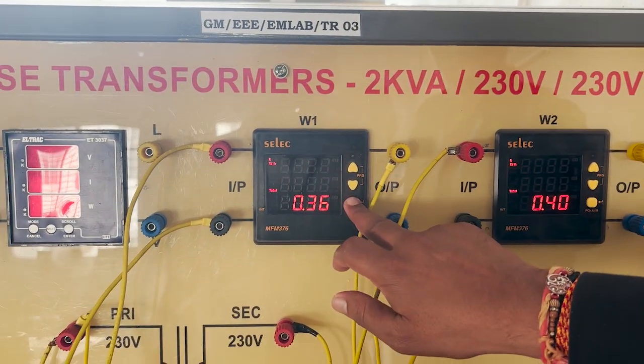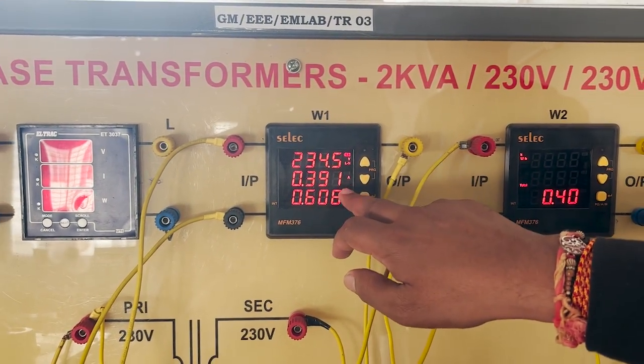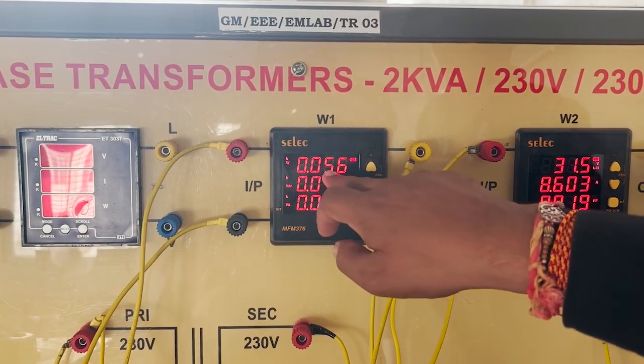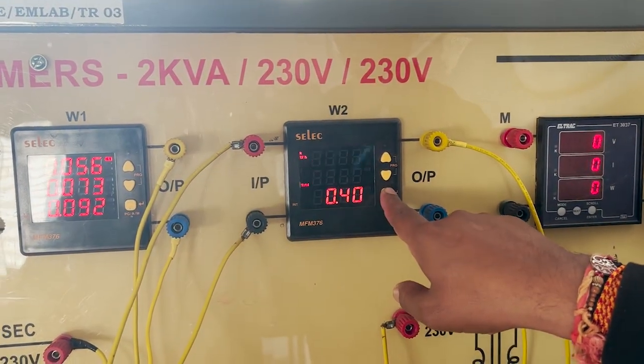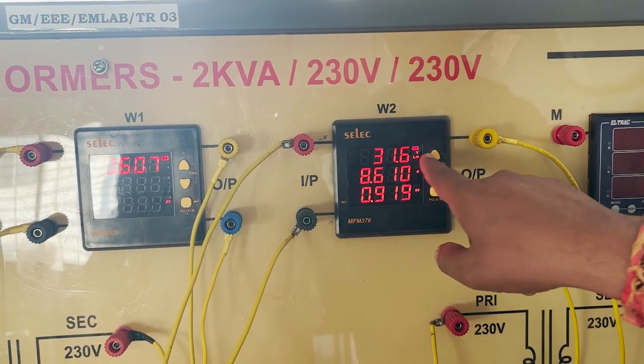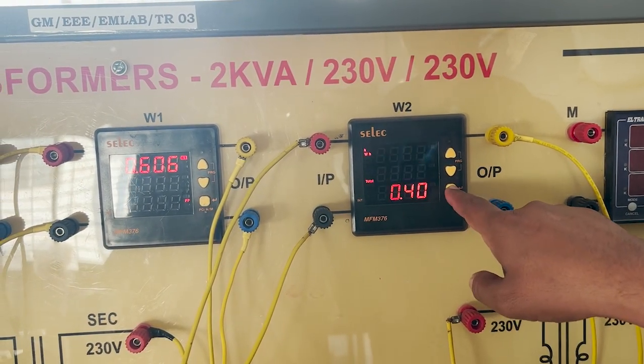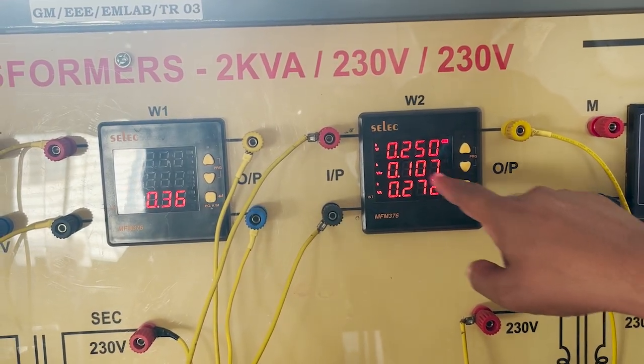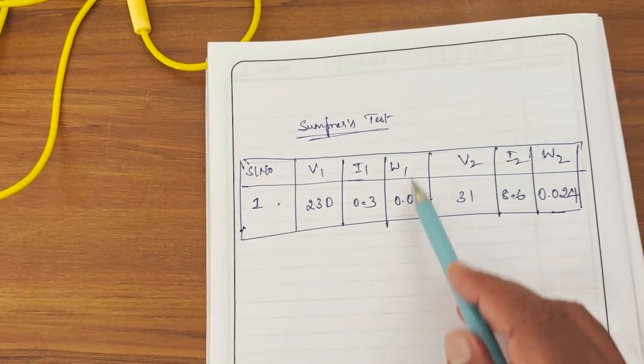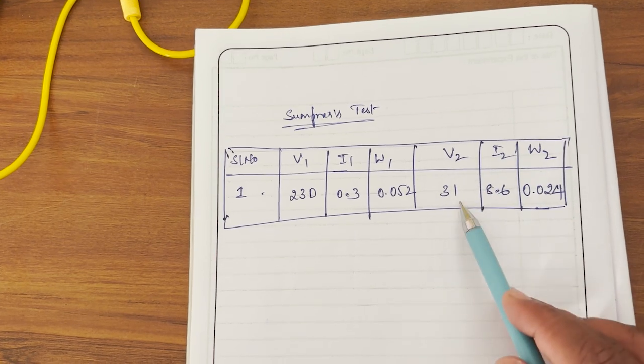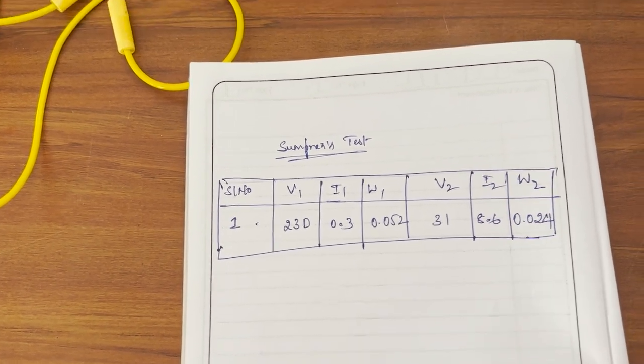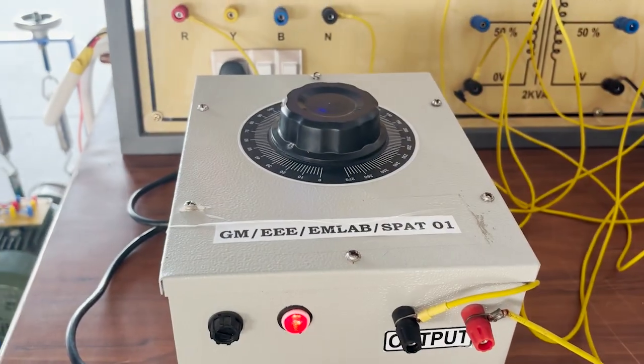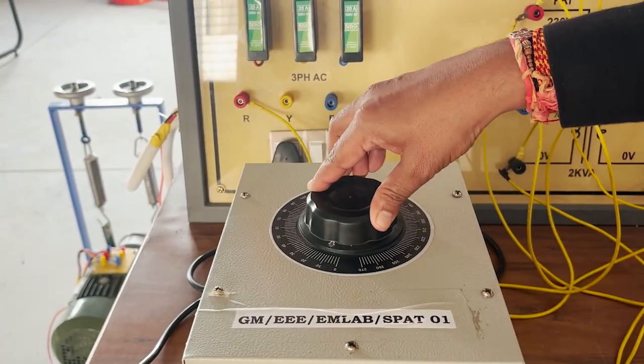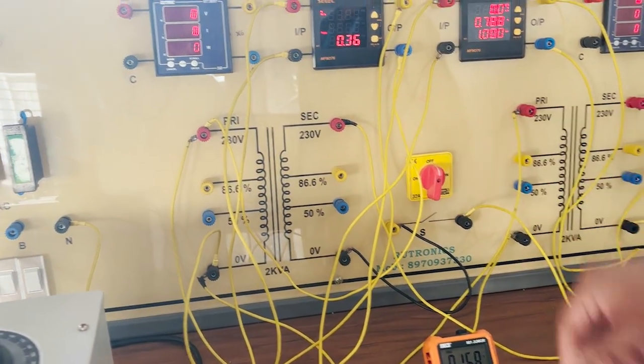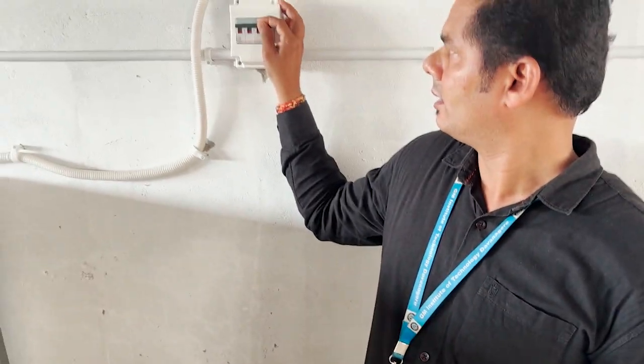Now we will take the readings, that is V1 is 234, I1 is 0.39, W1 is 0.056. Now W2, that is V is 31.6, 8.6 is the current and W is 0.250. Now you can see the reading: V1 is 230, I1 is 0.3, W1 is 0.052, V2 is 31, I2 is 8.6, W2 is 0.024. Now you have to reduce the voltage and turn off the switch, then disconnect the main supply. Thank you.